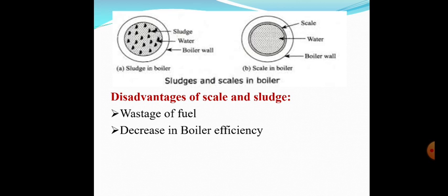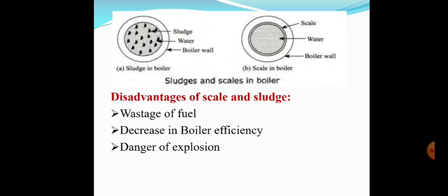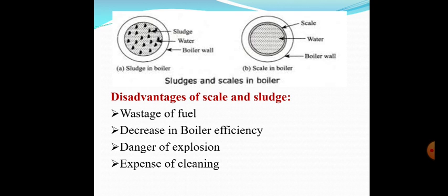The third disadvantage is danger of explosion: due to scale and sludge formation, when the boiler is overheated the metal expands while the scales and sludge do not expand as much. Due to this, the scales crack and water from inside the boiler comes in contact with the hot metal, immediately forming steam. This steam exerts pressure on the boiler walls, which may crack and cause the boiler to explode. The fourth disadvantage is the expense of cleaning, and the fifth is lowering of boiler safety.